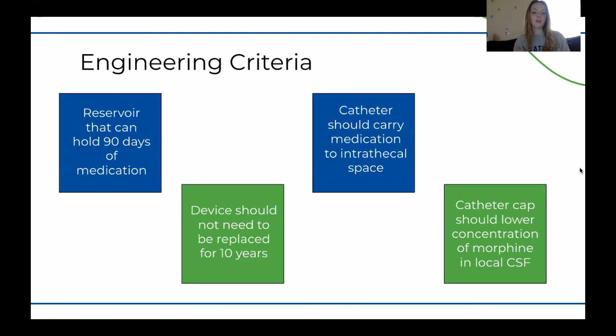The reservoir part of the device must be suitable so that it can hold 90 days worth of medication, and the catheter must be able to carry medication from this reservoir to the intrathecal space, and our newly developed catheter cap must lower the concentration of morphine in the local cerebrospinal fluid to avoid inflammatory granulomas. The spinal cord stimulation aspect must have the electrodes that carry the stimulation to the epidural space, and this must run from 0 to 20 milliamps and 2 to 1200 hertz.